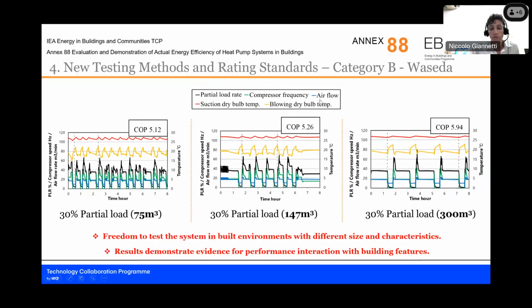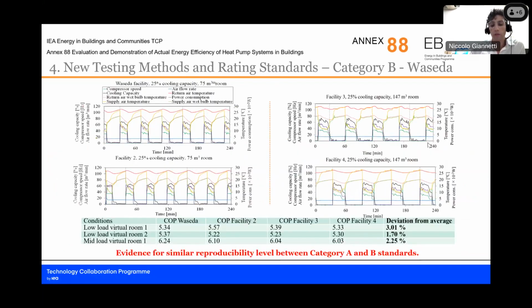Then the emulator, so the software side, gives us the freedom to simulate any building feature, in this case, different building size with different building inertia. So this is a virtual building, but the system obviously responds with different dynamics to the same load, but with different thermal inertia of the indoor space, leading to also different COP. And reproducibility studies have been conducted within different facilities, and we could observe that addressing all these sources of thermal delay and transport delay, results could be accurate and reproducible within 3%.